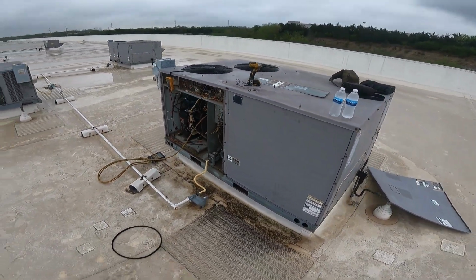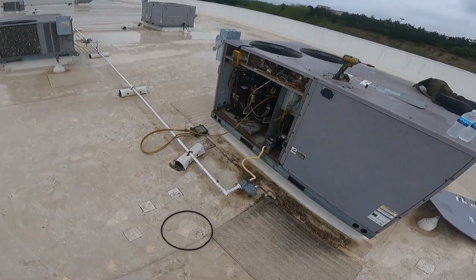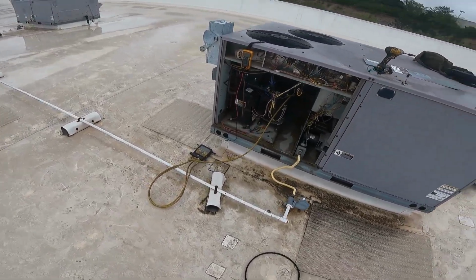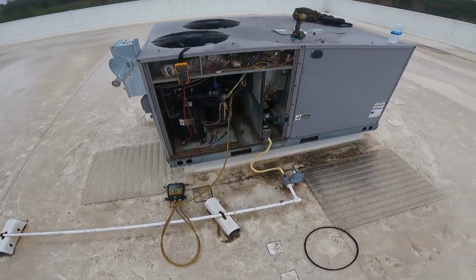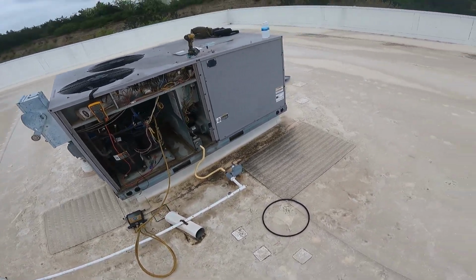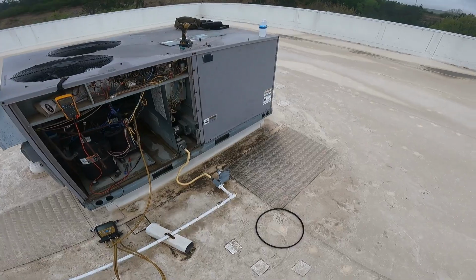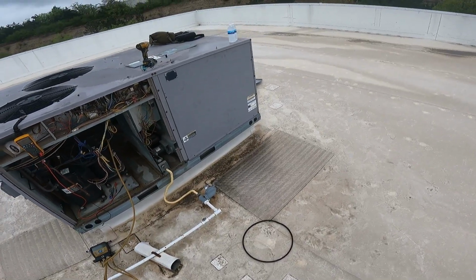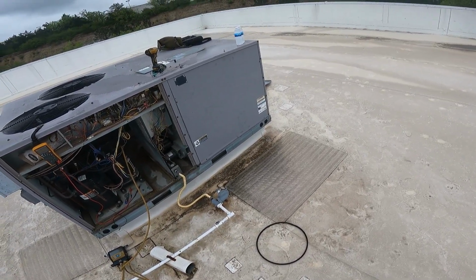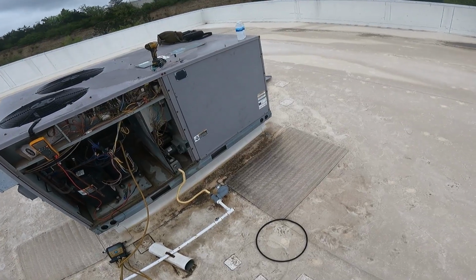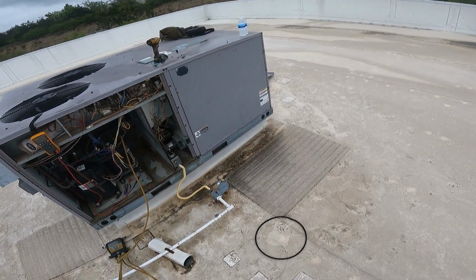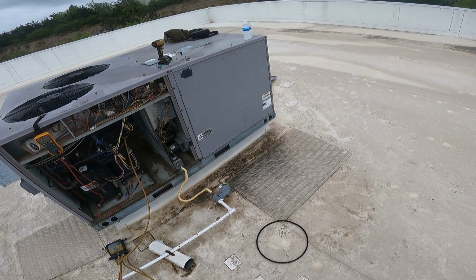We're gonna have to replace the piece of copper that is kinked. So there's recovery on stage 1. Stage 2: nitrogen, two dryers, heat exchanger, heat exchanger brackets. Always do the limit switches when you do a heat exchanger. So: limit switch, rollout switch.